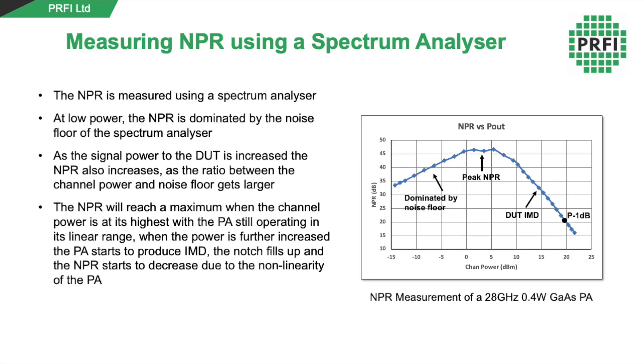At low power, the noise power ratio is dominated by the noise floor of the spectrum analyzer, and as the signal power to the DUT is increased, the noise power ratio also increases. However, when the device under test starts compressing, the noise power ratio will then decrease, and we can use this as a measure of linearity.